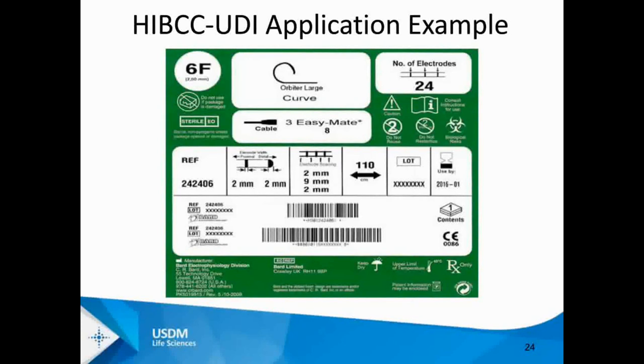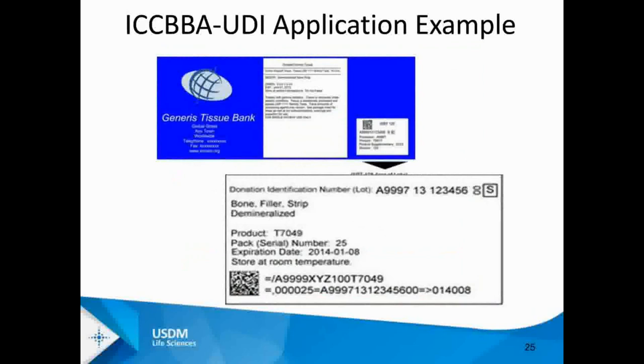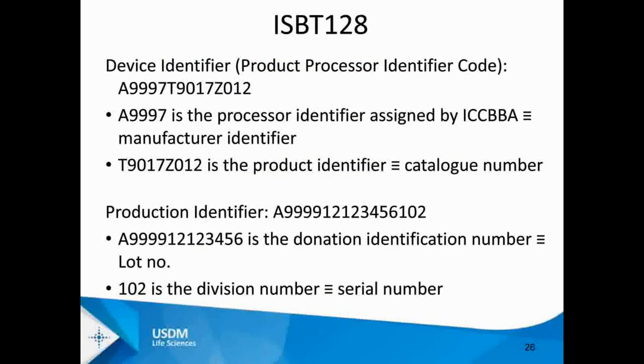Standards are relatively technology-neutral, so different technologies can be used, and you may use different barcodes on different packaging levels. A HIBCC-built UDI works similarly: top barcode contains the device identifier, bottom barcode contains lot number and expiration date. For tissue products regulated as devices, ICCBBA's ISBT-128 standard applies, which includes a donation identification number as a production identifier. Manufacturers of tissue products regulated as medical devices should contact ICCBBA, as ISBT-128 also fulfills tissue tracking requirements.